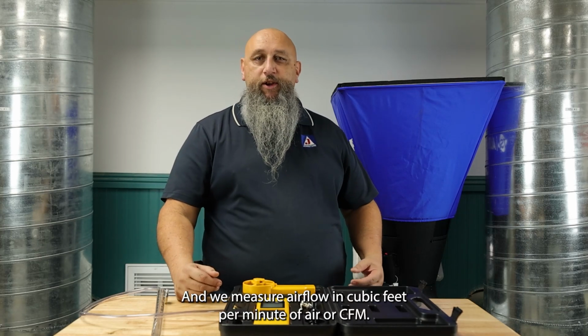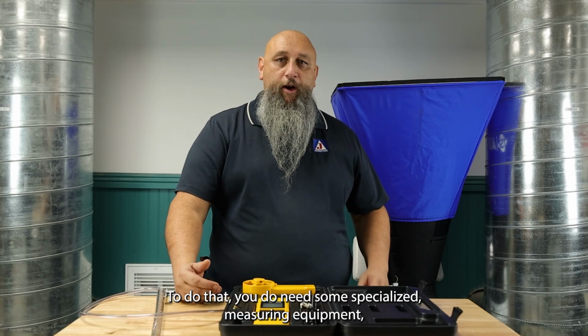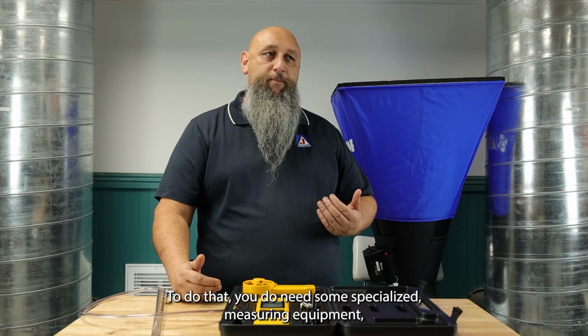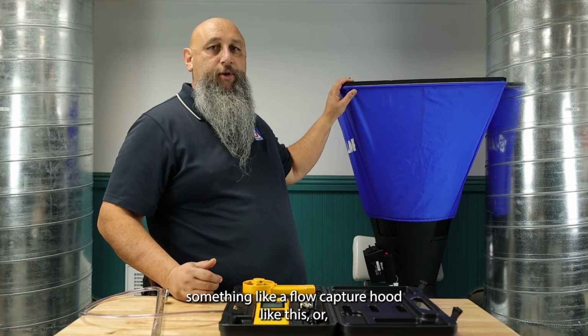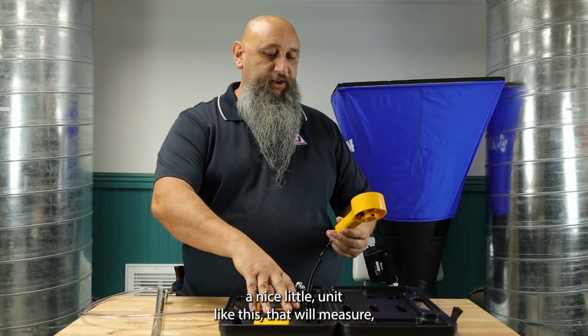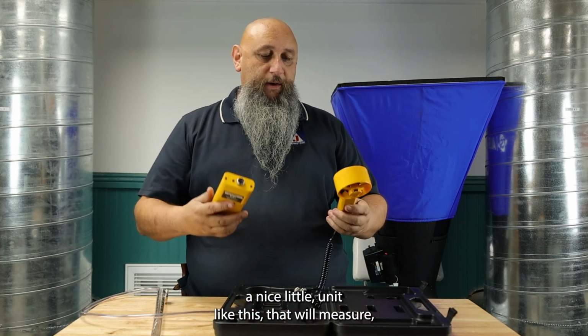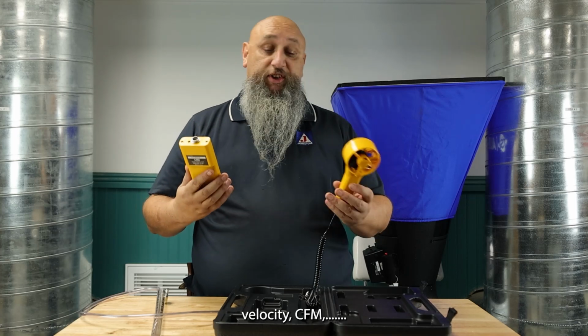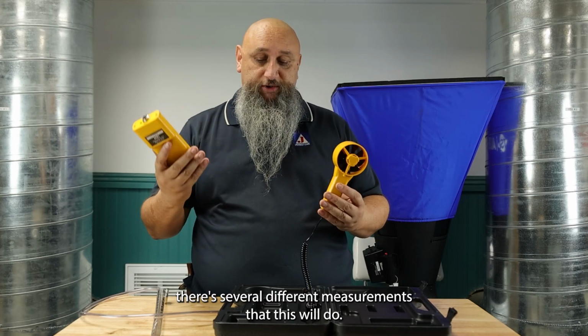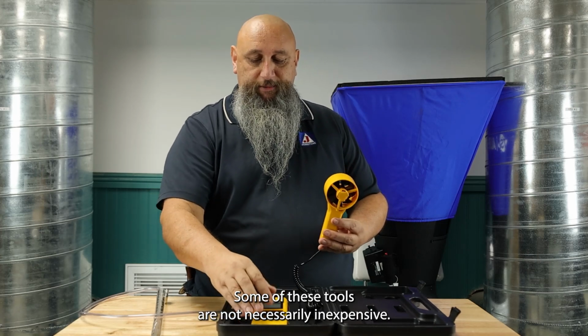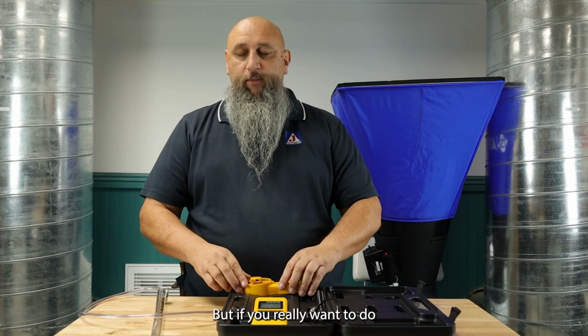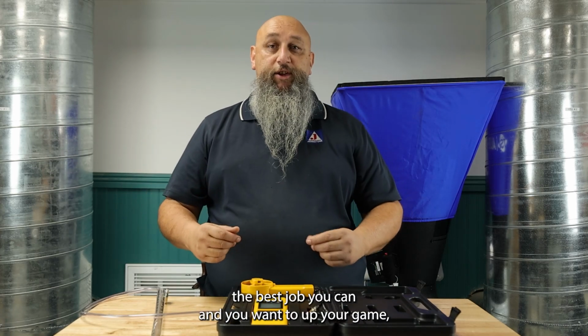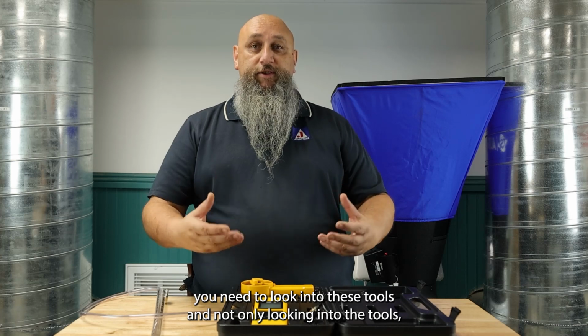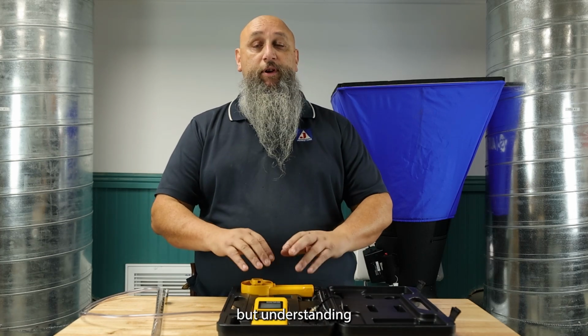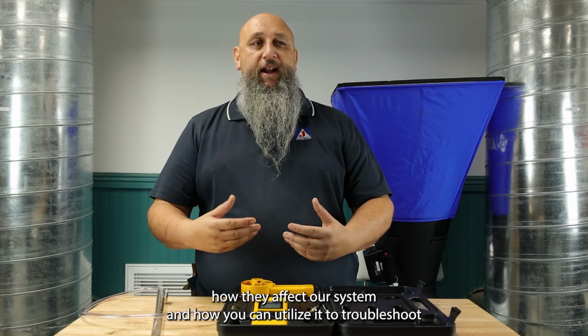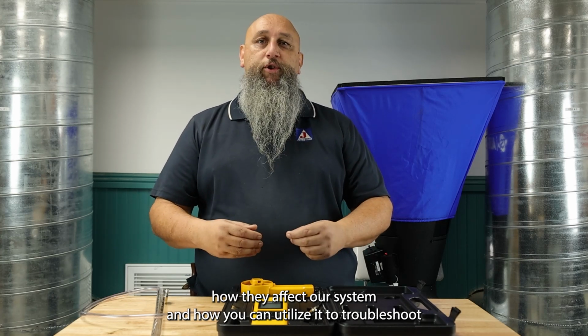And we measure airflow in cubic feet per minute of air, or CFM. To do that, you do need some specialized measuring equipment, something like a flow capture hood like this, or a nice little unit like this that will measure velocity, CFM. There's several different measurements that this will do. Some of these tools are not necessarily inexpensive, but if you really want to do the best job you can and you want to up your game, you need to look into these tools, and not only looking into the tools, but understanding how they affect our system and how you can utilize it to troubleshoot and give a better performance to your customer.